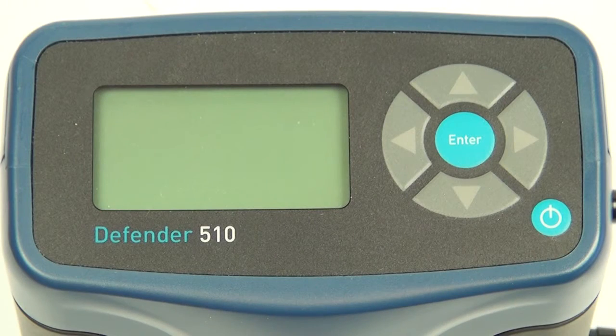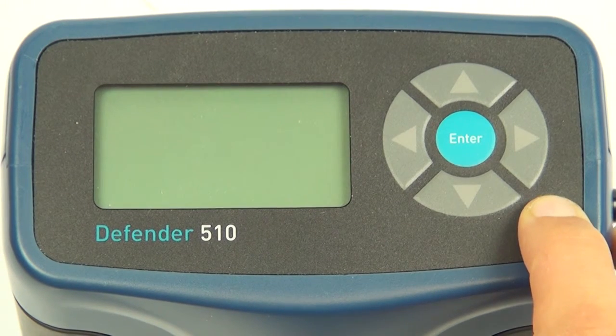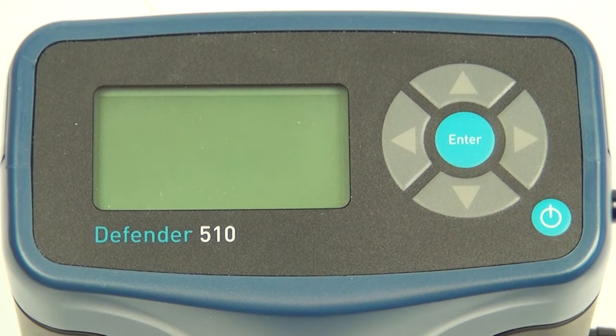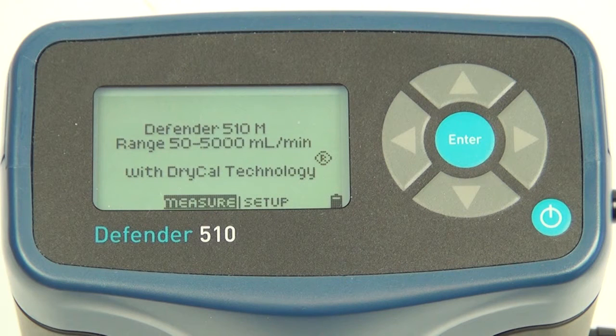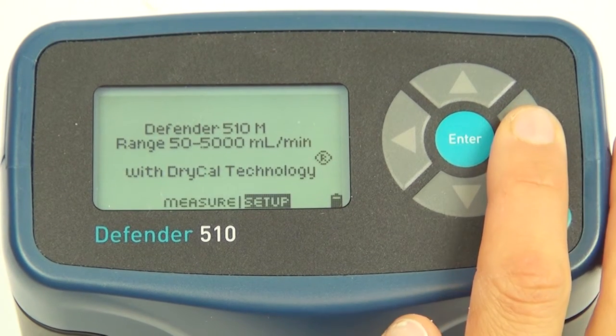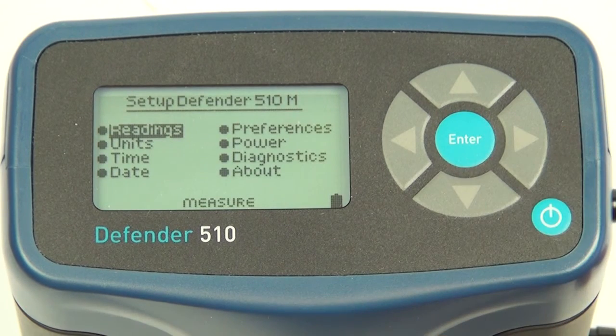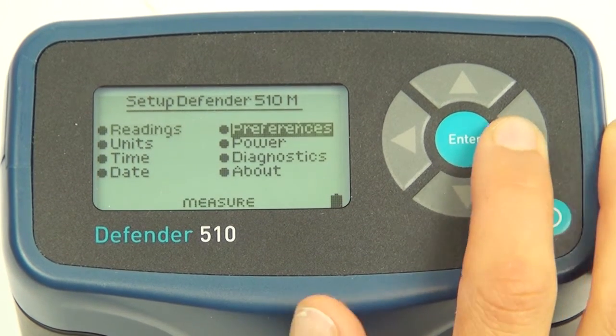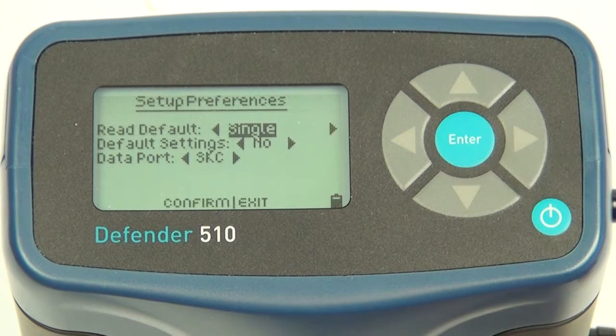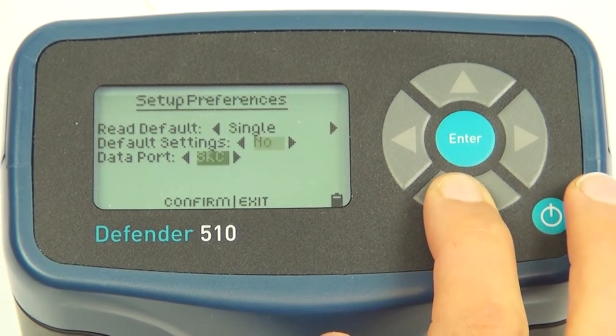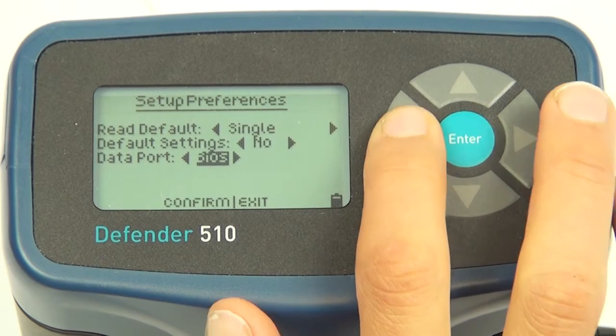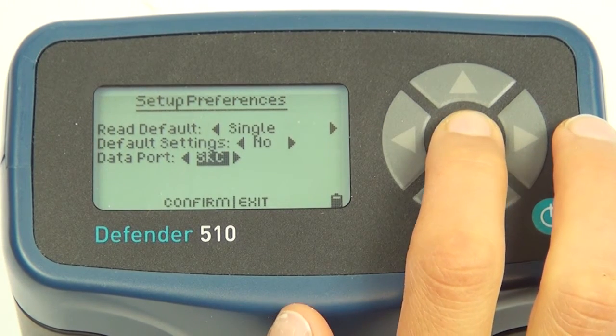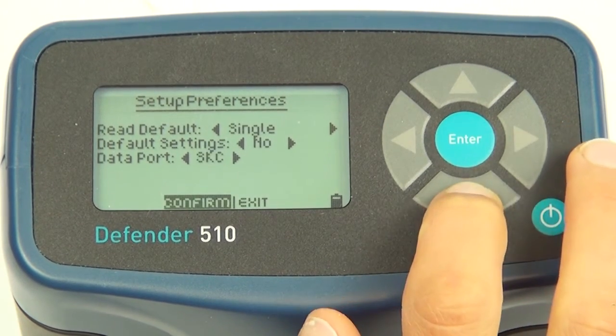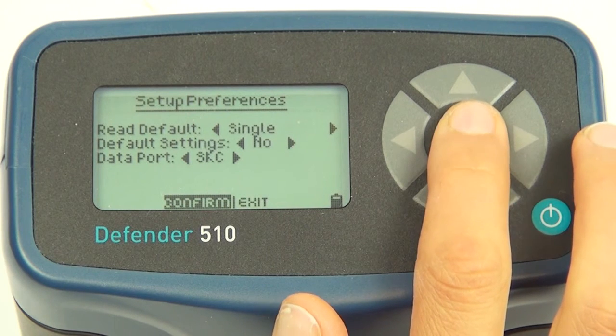Now press and hold the power button on the Defender calibrator until the piston moves. You hear a click and the screen lights up. To select the Defender data port, press the right arrow to highlight Setup and press Enter. Press the right arrow to highlight Preferences and press Enter. Press the down arrow to navigate to Data port and press the left or right arrow to toggle to SKC. Press the down arrow to highlight Confirm and press Enter.